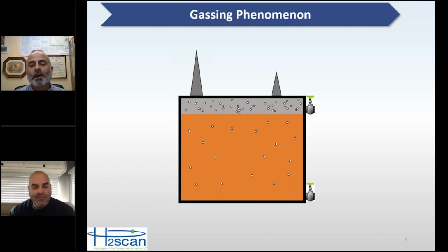And as your oil moves around your transformer, which varies based on ambient temperature, your load on your transformer, and how hot, what cooling you have on, a lot of different variables come into play as to how long it takes that hydrogen to reach equilibrium around your transformer and in the oil.